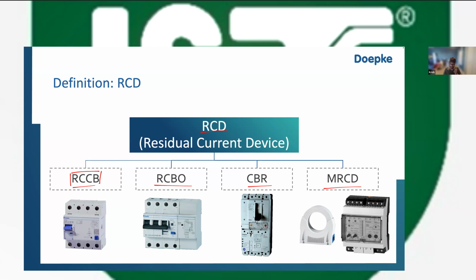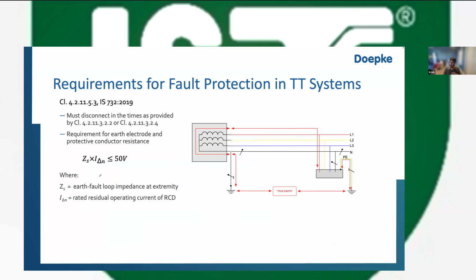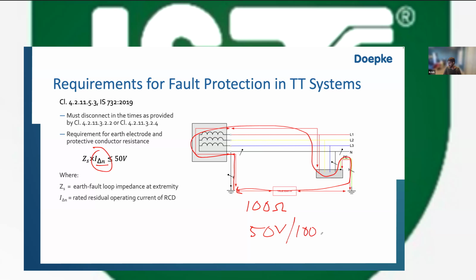Firstly, if we go to the slide that I have on this value, you need to measure the fault loop impedance in your TT system and see what this fault loop impedance is. Say you measure it is 100 ohms. Then 50 volts divided by 100 ohms gives you this value of I delta. So 50 volts divided by 100 ohms is equal to 0.5 amperes or 500 milliampere. In this particular case, anything less than 500 milliampere or 0.5 ampere is appropriate.